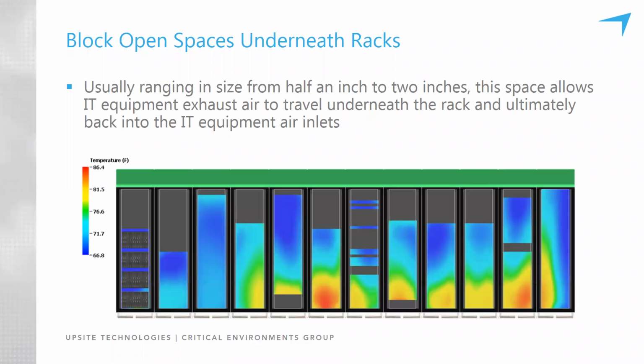As Rob mentioned, many cabinets are delivered with casters or leveling feet, and this creates a space underneath the cabinets. Most people tend to think of the hottest location in a cabinet being at the top of the cabinet, but many times in computer rooms, I've found the highest intake temperatures located at the very bottom of the cabinet. Might be the very bottom 1 or 2 U in the cabinet. And this is the result of hot exhaust air circulating underneath the cabinet and flowing into the IT equipment intakes. Now, the problem cannot be solved in many cases by adding more conditioned air or colder conditioned air. It's simply that the exhaust air flowing under the cabinets is displacing the conditioned air that's there and available.